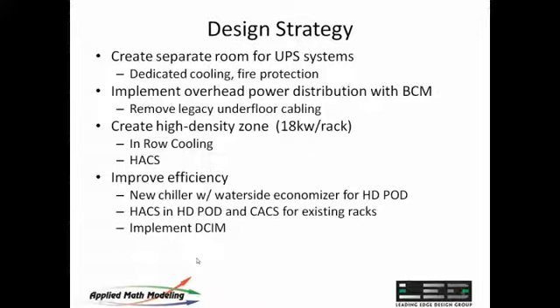The next piece, in order to support the highly virtualized loads and the 18 kW per rack projection, was to take a zone approach. We created a high-density zone utilizing in-row cooling and hot aisle containment, really creating a self-sustained pod specific for the highly virtualized loads and high-density equipment expected in the data center. That's where they saw the growth in their IT environment, so we needed infrastructure to support those types of loads.